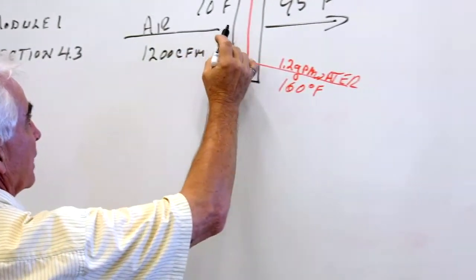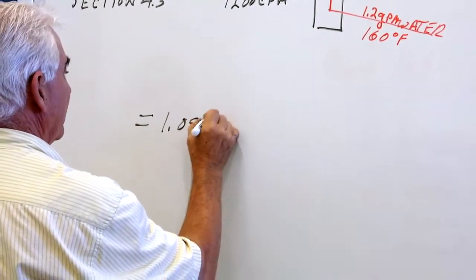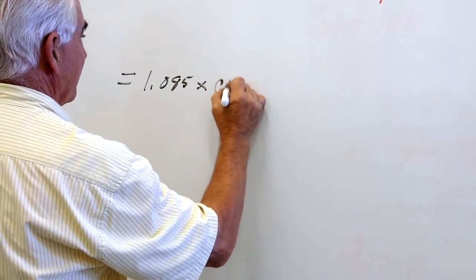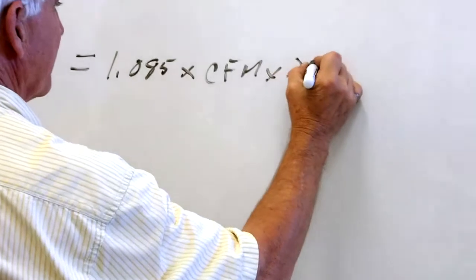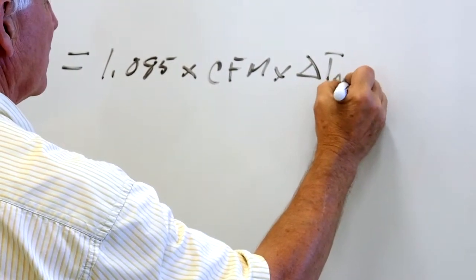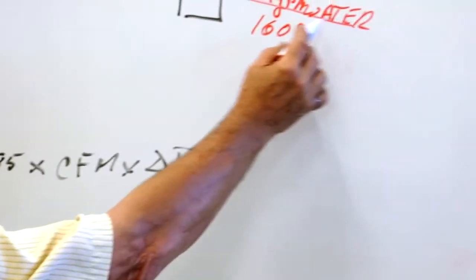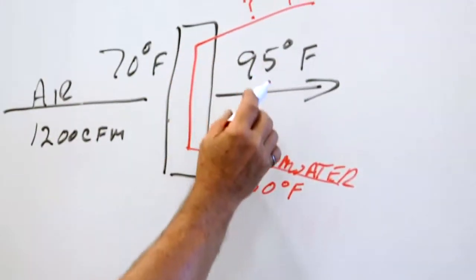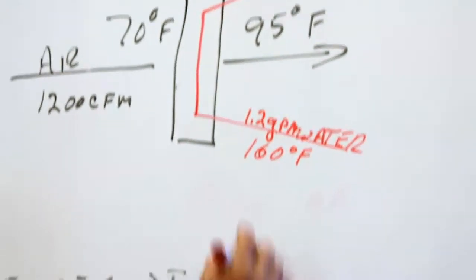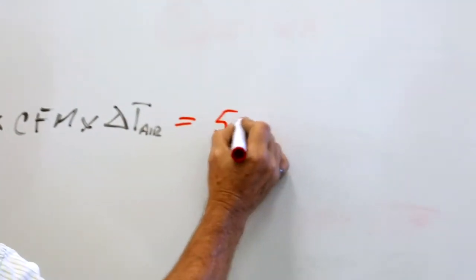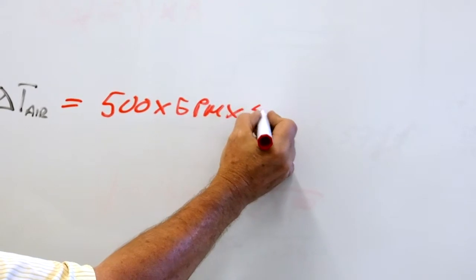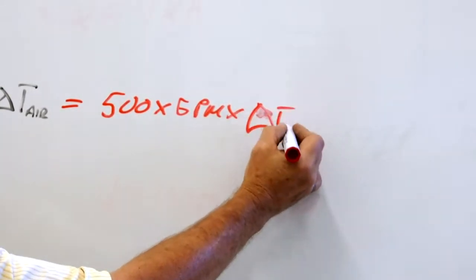We have two equations that we use. One equation is: BTUs per hour gained by the air equals 1.085 times the CFM times the difference in temperature of the air. And we have another one that relates to the amount of energy given up by the water to the air, which equals 500 times GPM times the delta T of the water.